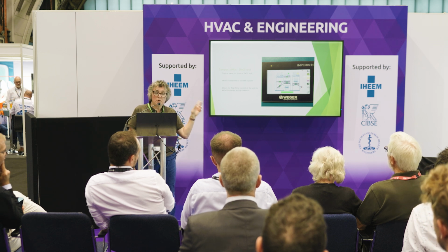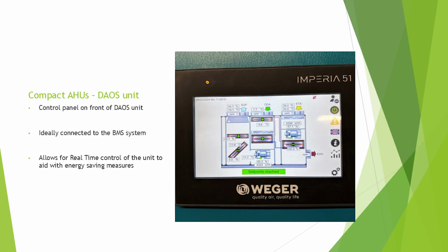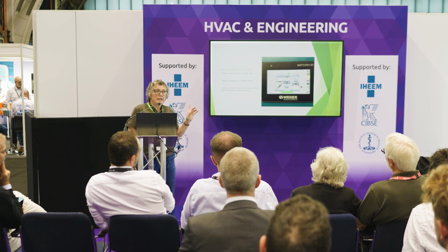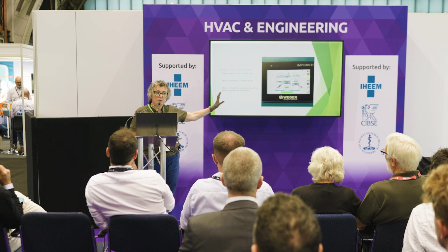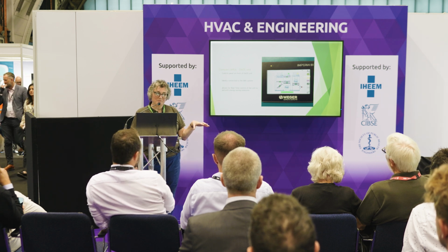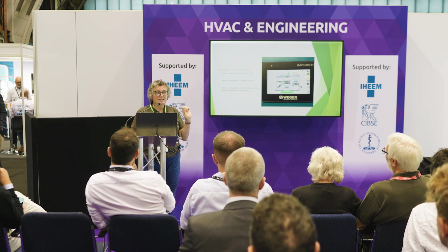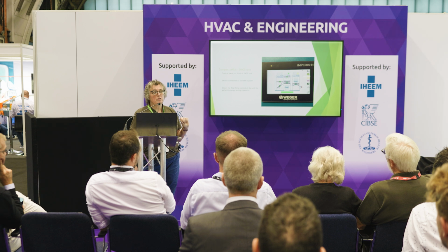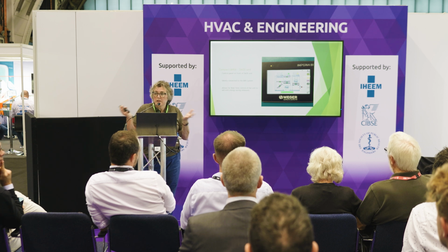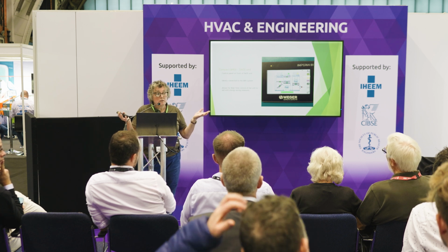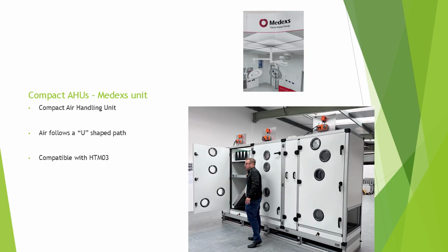Ideally, that would be connected to the BMS. In this case, there was a mismatch between this unit, which was very modern, and the BMS system, which was very old. So, as far as I understand it, they didn't quite get that connectivity immediately, let's just say. But they could walk into the plant room and look at the front of it to find out what state it was in. But that's just what happens when you upgrade technology. You don't always get the things to talk to each other in the first instance.